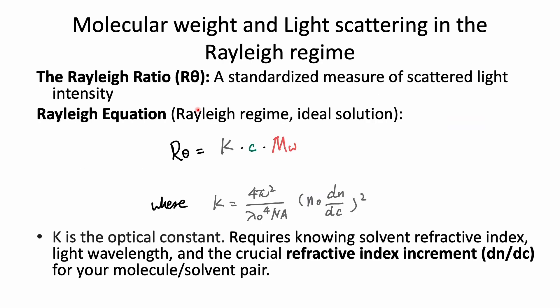Now we understand the basics of Rayleigh scattering. To measure molecular weight, we use an equation called the Rayleigh equation. On the left is the Rayleigh ratio, a standardized measure of scattered light intensity. On the right, there is concentration, weight-average molecular weight, and K — the optical constant. K can be expressed as: K = (4π²n₀²(dn/dc)²) / (Nₐλ⁴), where λ is the wavelength of the incident laser, Nₐ is Avogadro's number, n₀ is the refractive index of the solvent, and dn/dc is the refractive index increment — a measure of how the refractive index changes with concentration of the sample in the solvent. Normally you need to measure dn/dc with a specific instrument.